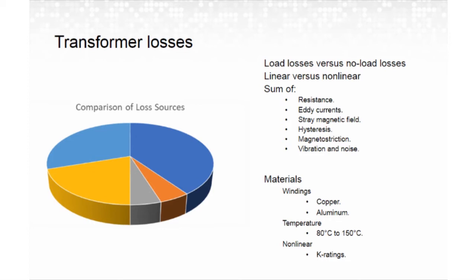And then as we load that up more, we create more flux losses and stray magnetic field losses, which then induce eddy currents in adjacent surfaces, which is why they will start to vibrate. The casing will vibrate more at higher loads. And anytime we're trying to mitigate those from a building standpoint, we're looking at vibration isolation on not only the transformer, but any of the conduit supports that connect that transformer rigidly to the rest of the building system and structure. Just vibration isolation on the transformer pads alone usually isn't sufficient.